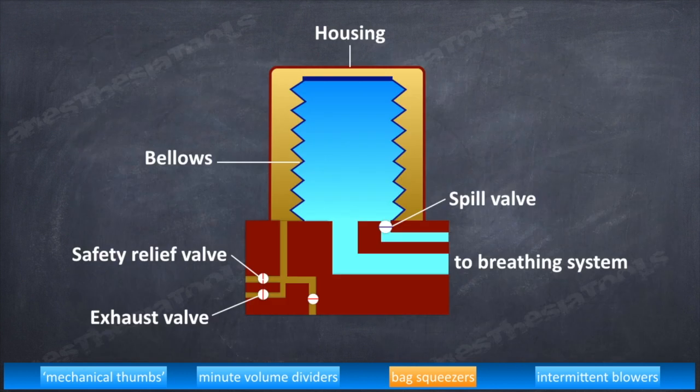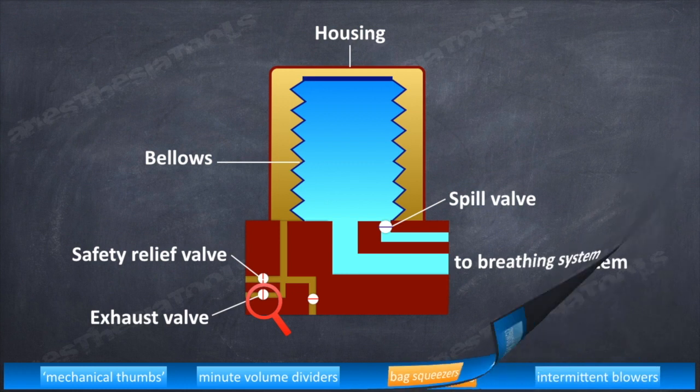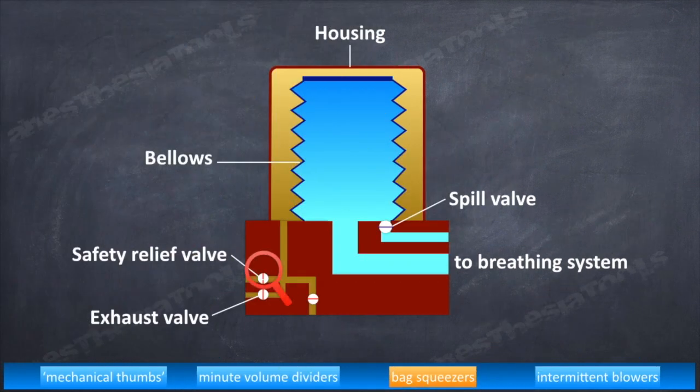Now into graphical representation of the functioning of ascending bellows ventilators. The bellows is contained within the clear housing. The driving gas from the ventilator does not ventilate the patient directly. The bellows is filled by fresh gas flow or patient gas when in use and attached to a breathing system. In the diagram, please identify the drive gas inlet, exhaust valve, and safety relief valve. You may also note the spill valve for gas within the bellows, which opens on excessive pressure within the bellows.